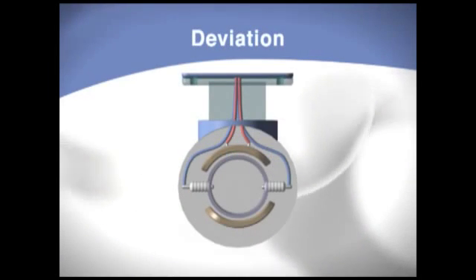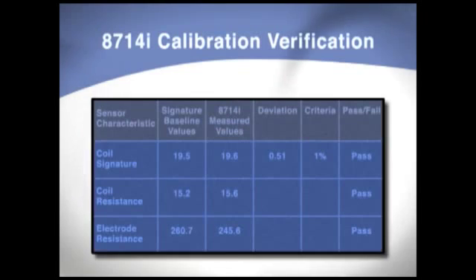Any shift in the meter's calibration will show up as a shift in the magnetic signature values and be detected by the 8714i. If this happens, the diagnostic will notify you to recalibrate the meter.